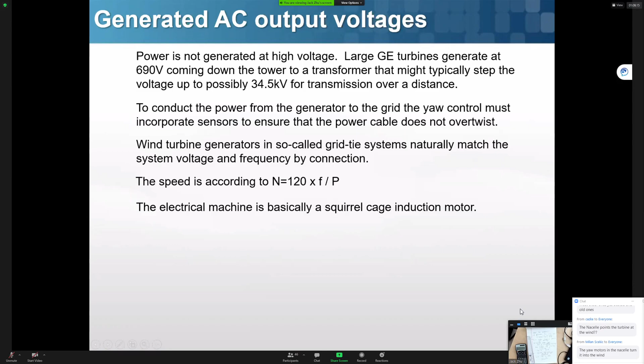Some of those wind turbine generators are called asynchronous generators. They're basically a squirrel cage induction motor. When that motor's rotor turns faster than the rotating magnetic field of the stator, it becomes a generator. That's why they call them asynchronous generators. For example, a motor with full load at 1750 RPM as a motor - we can figure out 1800 RPM is probably the synchronous speed, so it's probably a 4-pole generator. When this rotor is turning at a speed of 1850 RPM, this motor will become a generator.